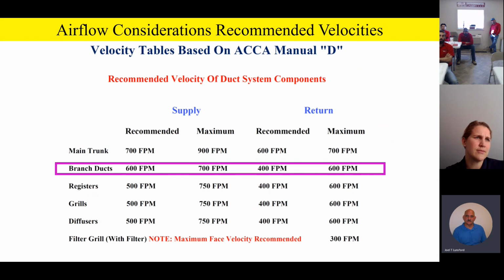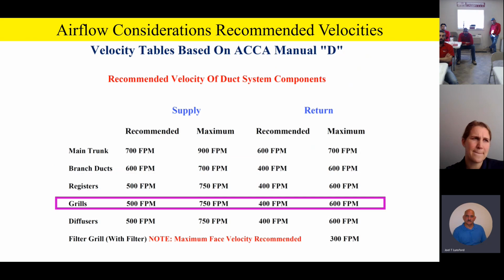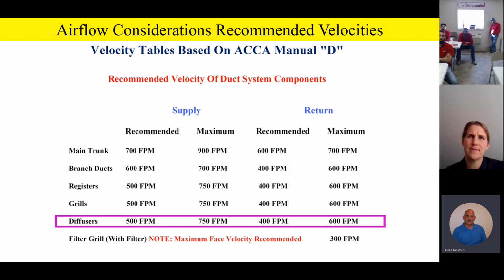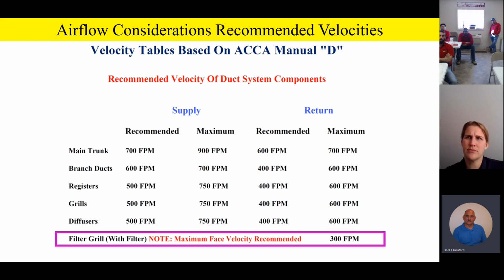Your takeoff should be about 600 and 400 on the return. Registers and grills need to be about 500 and 400 on return. Diffusers are about the same. And remember, if you have a filter grill, or a return grill with a filter in it, don't exceed 300 feet a minute velocity across that filter. And again, all of this stuff is right out of Manual D.